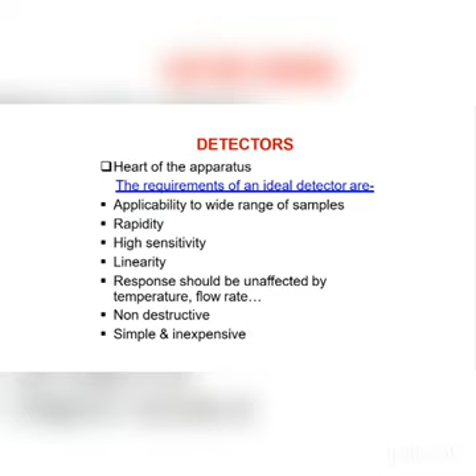Now the detectors. The detectors are the heart of the apparatus. The requirements of an ideal detector are that it has applicability to a wide range of samples and a rapid response with high sensitivity and linearity. The response should be unaffected by the temperature and the flow rate. It is non-destructive, simple and inexpensive.